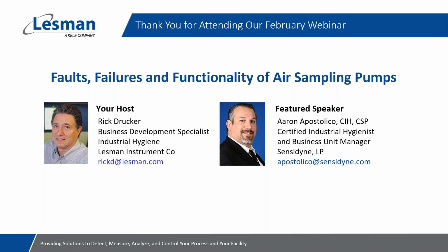If you end up pulling any type of liquid into the pump itself, of course it could potentially damage the pump. But if you're just worried about how it's going to act or if it's going to react with the solvent in the air, generally I would say the pumps are really safe. They've been tried and tested true in those environments over several decades. And we really haven't had problems with them.